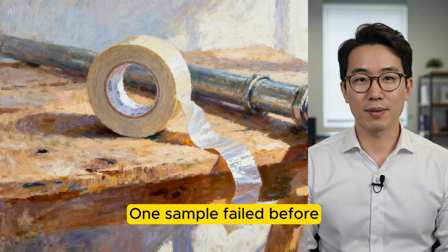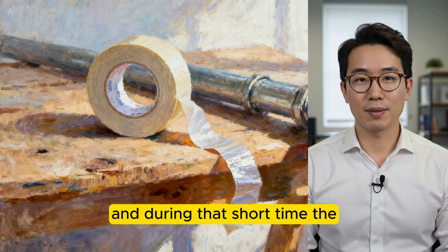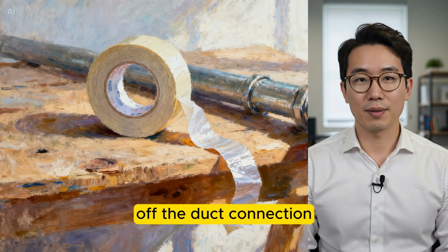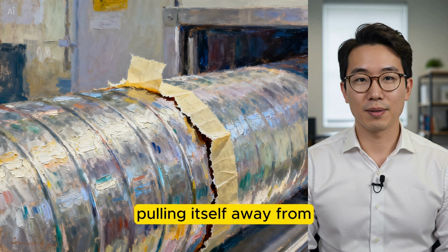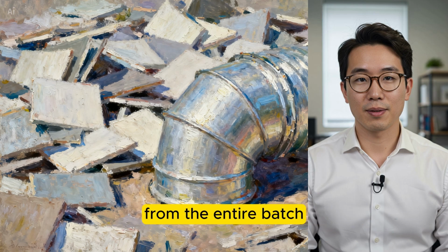One sample failed before testing even began. It had remained on a workbench for 1 week, and during that short time, the tape curled itself off the duct connection while trying to return to its original shape. The material was literally pulling itself away from the duct before entering the machine. Only one cloth-backed tape survived from the entire batch.